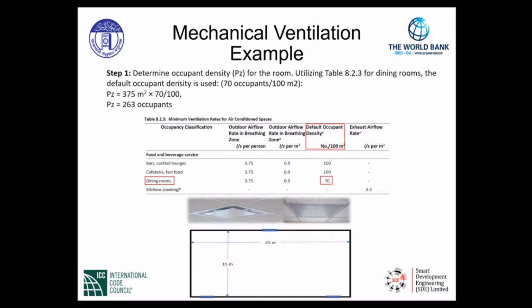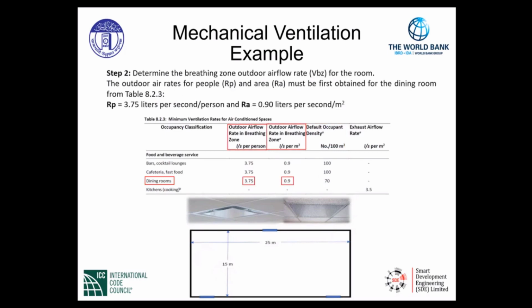Therefore, P sub Z equals 375 square meters times 70 divided by 100. This gives us 263 occupants. That is our P sub Z value, our population of the zone for ventilation. Step 2, we will determine the breathing zone outdoor airflow rate V sub BZ for the room. The outdoor air rates for people, R sub P, and the area outdoor air rates, R sub A, must first be obtained for the dining room from table 8.2.3.